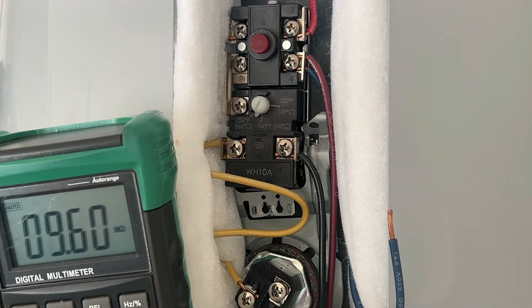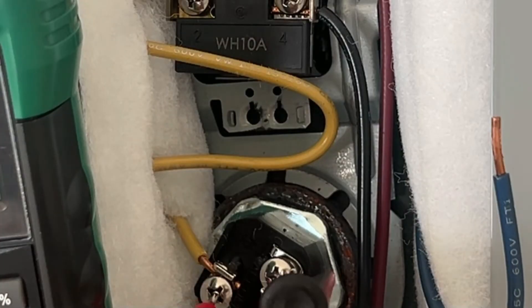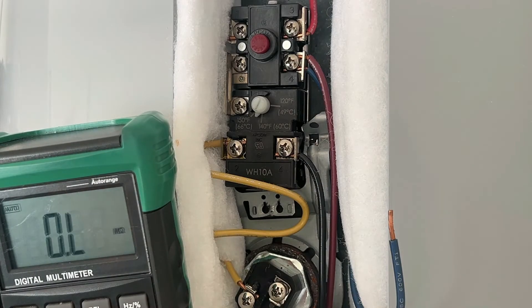We can also check the heating element itself by measuring its resistance. With the blue wire disconnected, we've got 9.6 ohms across this heating element, so this heating element is working perfectly. That's what we do to test the upper thermostat and the upper heating element. Now let's go to the bottom one.